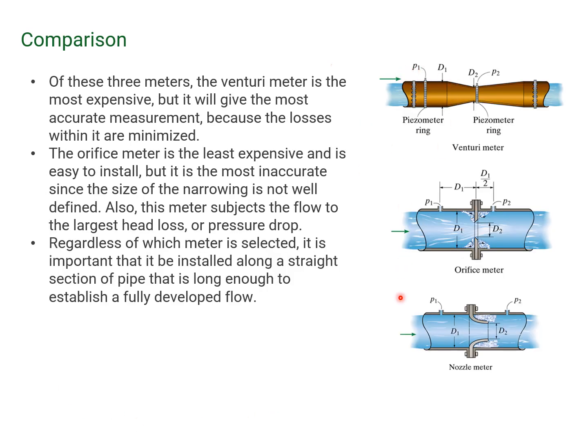Of these three basic meter types, which one is the best? The Venturi meter is the most accurate because losses within it are minimized. The orifice meter is the least expensive and it's very easy to install, but it's also the most inaccurate.